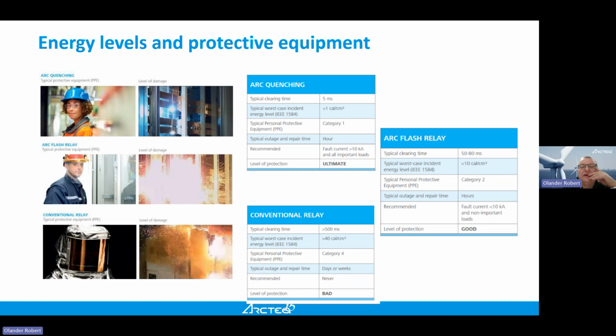Here you can see we have 3 different systems represented: a normal arc flash protected system with an arc flash relay, an arc flash relay plus a quenching device, which will eliminate the delay in the breaker, and then a conventional relay, and what type of protection you need in these different cases. So if you have a system with 30 kiloamperes, 50 kiloamperes, could even be 100 kiloamperes, if you let it burn for hundreds of milliseconds, it will be quite bad.